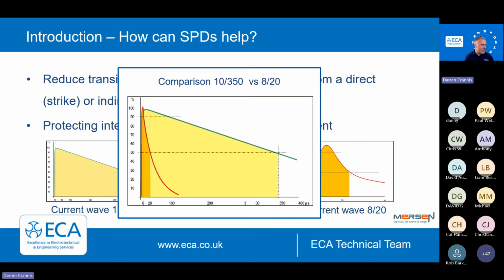Now, when we put these together, you can see the difference between a lightning strike, which is that large area of energy under the curve, and a switching transient. Switching transients are very short in duration and a very small amount of energy. And we can get this from MCBs, contactors, motors going on and off, elevators, electrical accidents, switching banks, welders, air compressors, switch mode power supplies. All these sorts of things can cause little transients and switching.